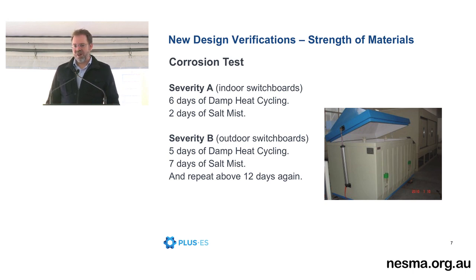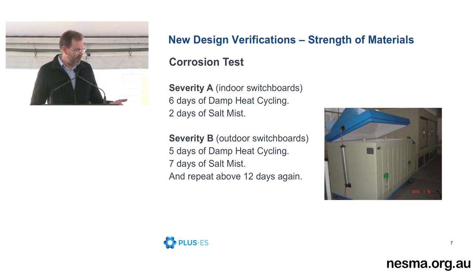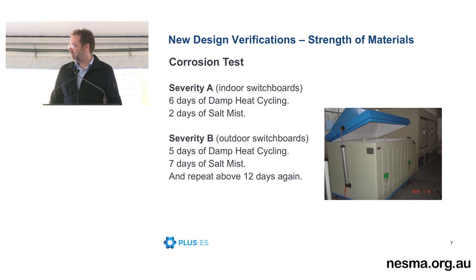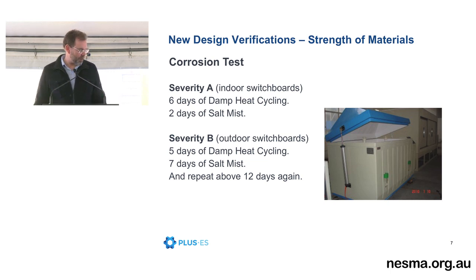I always find it interesting, you have the IP of an enclosure, and then you have the temperature rise, and these 2 things fight each other. With these new tests, we now have new villains, or new conflicts, such as the corrosion test affecting the ability to earth all your external components. So the old days of putting a star washer to cut through the paint, well, now it's cutting through your paint protection, and it's exposing a weak point in your corrosion performance. So yeah, there's a new villain.